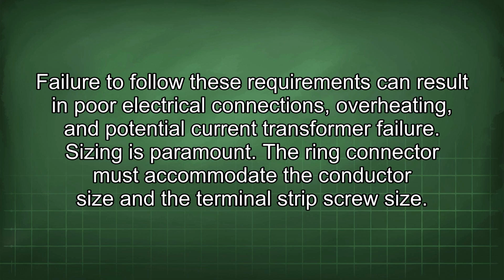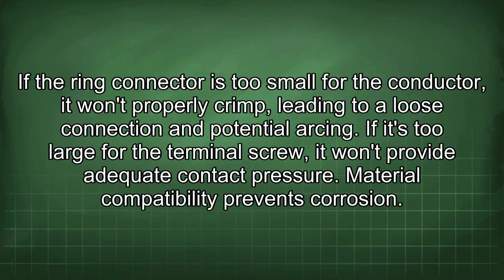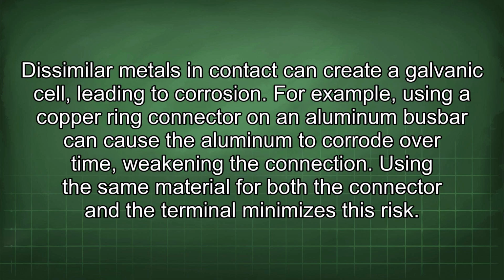Sizing is paramount. The ring connector must accommodate the conductor size and the terminal strip screw size. If the ring connector is too small for the conductor, it won't properly crimp, leading to a loose connection and potential arcing. If it's too large for the terminal screw, it won't provide adequate contact pressure. Material compatibility prevents corrosion. Dissimilar metals in contact can create a galvanic cell, leading to corrosion. For example, using a copper ring connector on an aluminum busbar can cause the aluminum to corrode over time, weakening the connection. Using the same material for both the connector and the terminal minimizes this risk.